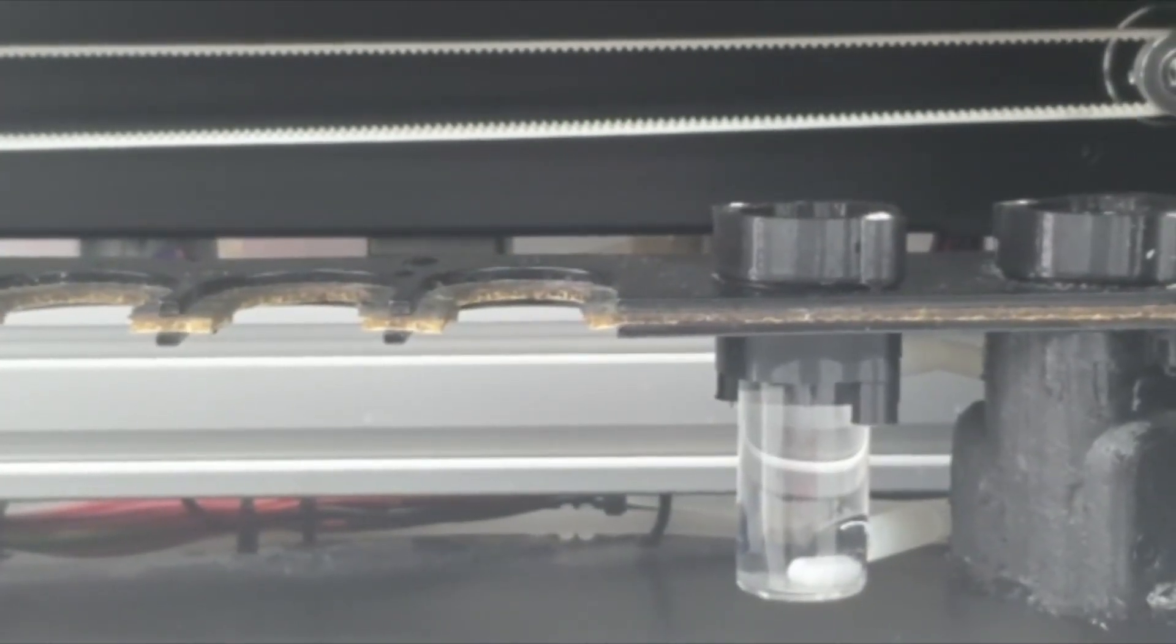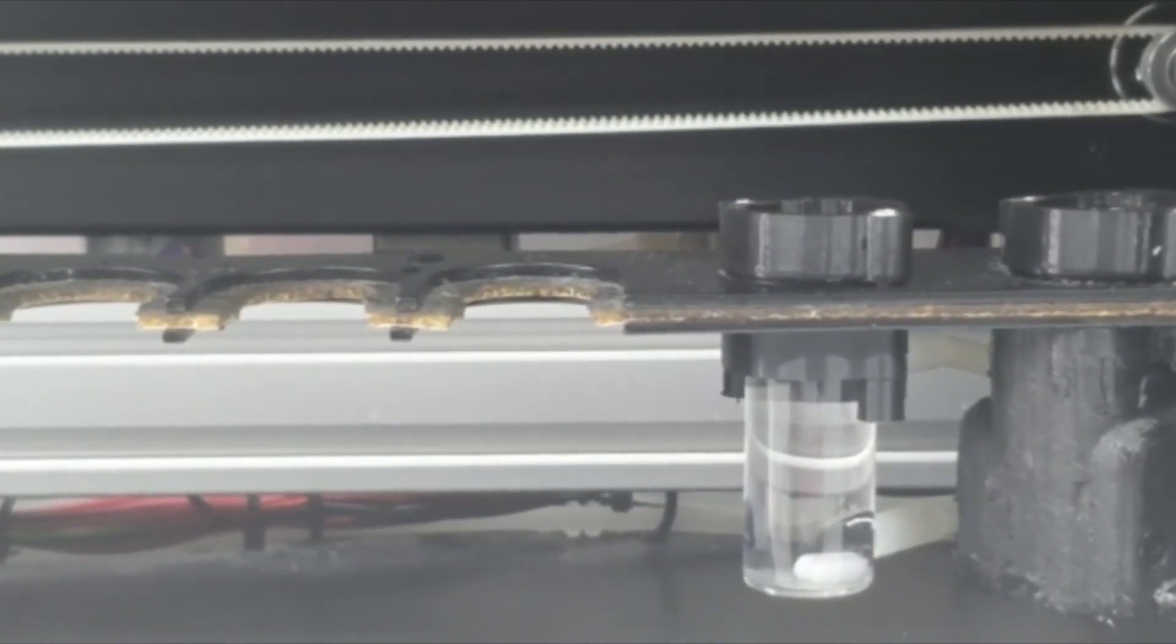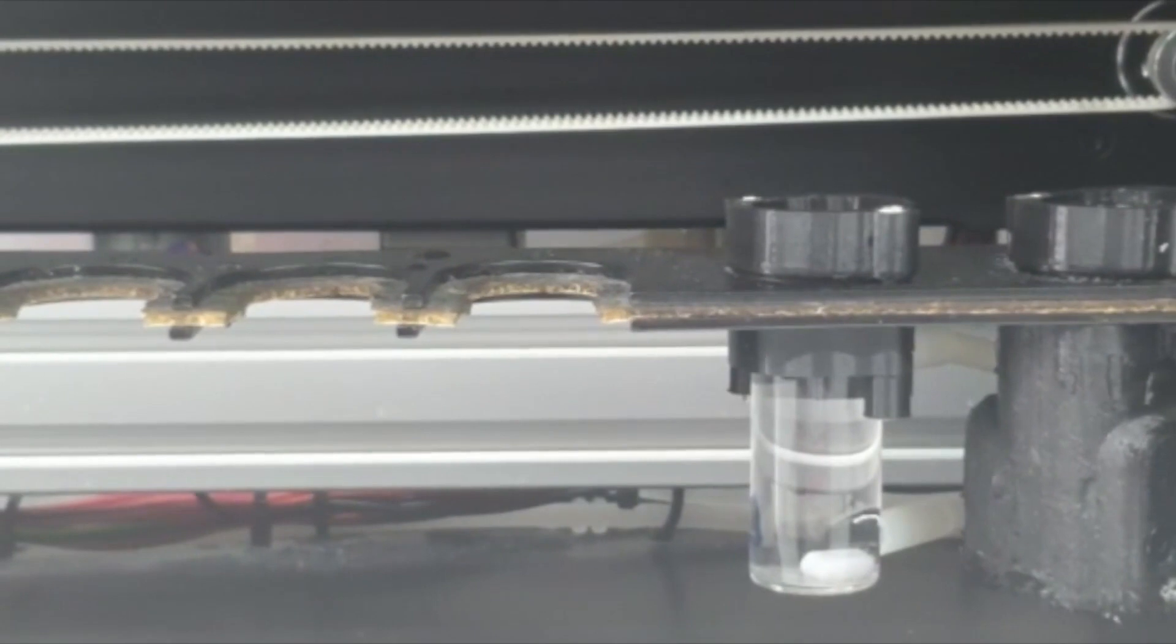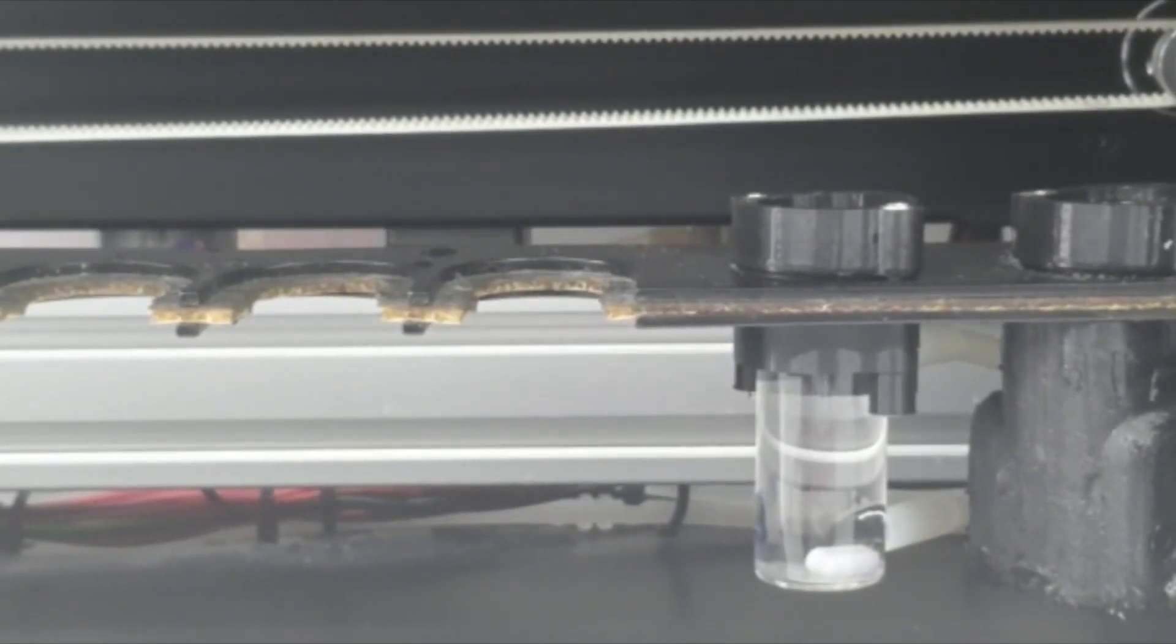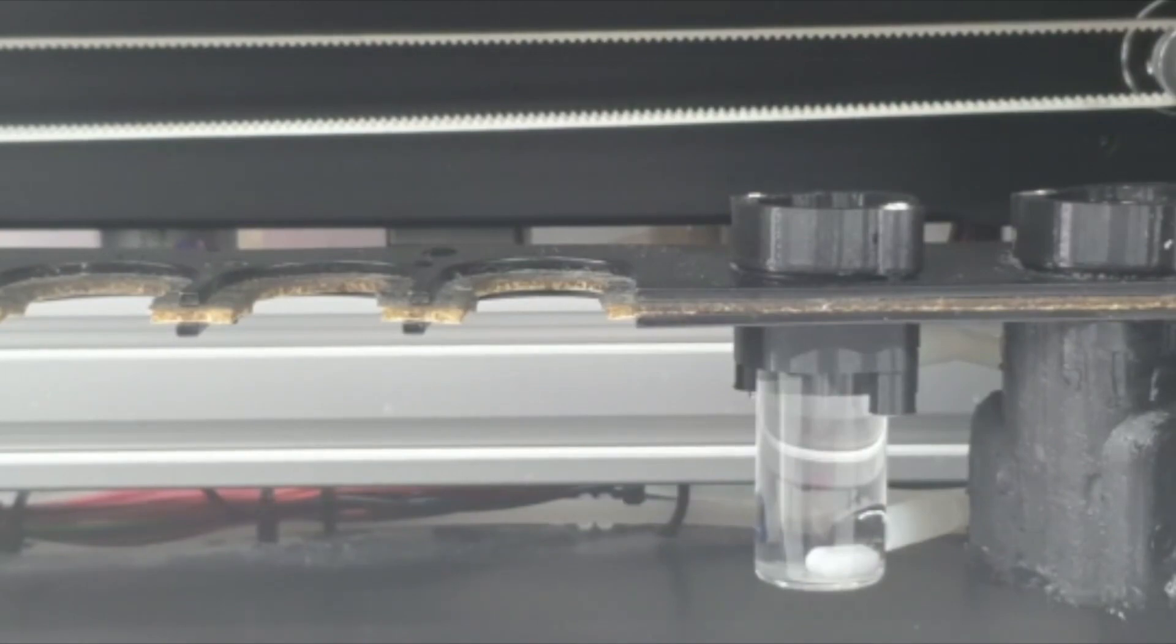Insufficient RO water is caused by improper calibration of the rinsing chamber, RO water not being enough in your tank, or the RO tube not being well immersed in your tank.